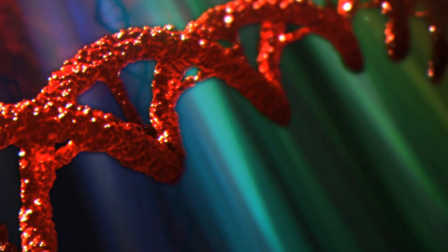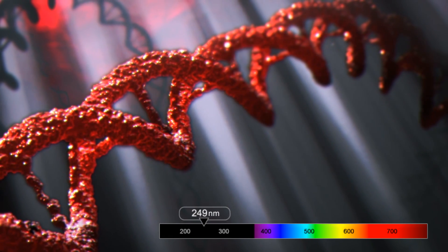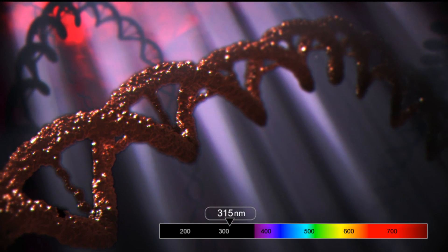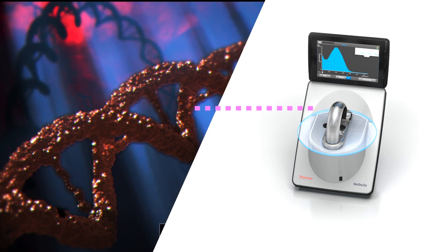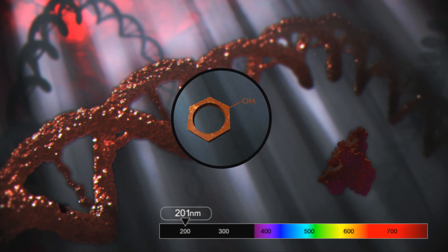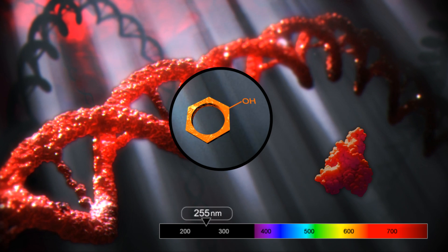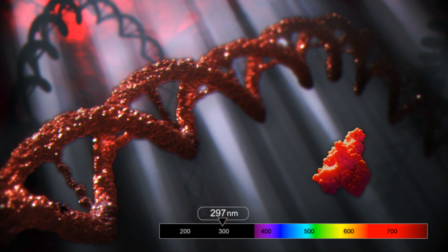Like fluorescence, the amount of light absorbed at 260 nanometers corresponds to the amount of nucleic acid present. Unlike fluorescence, absorption measures the total amount of nucleic acid present, including DNA, RNA, oligonucleotides, etc. Using fluorescence and absorption detection methods helps to dramatically increase the dynamic range of analyte detection. The absorption profile provided by the NanoDrop One instrument can be used to detect contaminants which may impact downstream applications. For example, proteins absorb at 280 nanometers; therefore, the absorbance 260 over 280 ratio can be used to estimate nucleic acid sample purity.